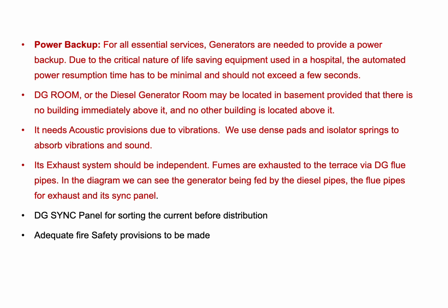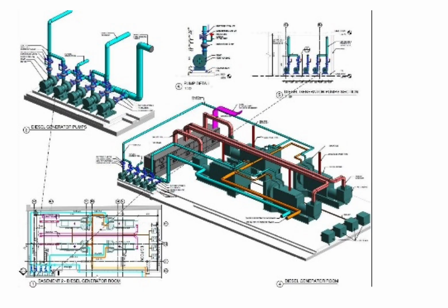We use dense pads and isolating springs to absorb vibrations and sound. Its exhaust system should be independent. Fumes are exhausted to the terrace via DG flue pipes. In the diagram here, we can see the generator being fed by the diesel pipes, the flue pipes for exhaust and its sync panel. Fire safety provisions for DG rooms are to be made adequately.